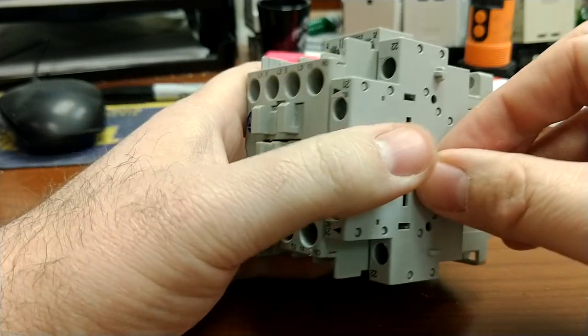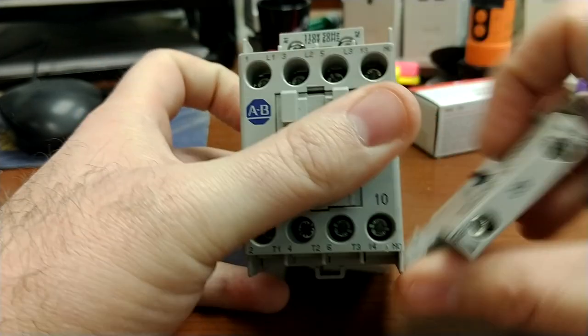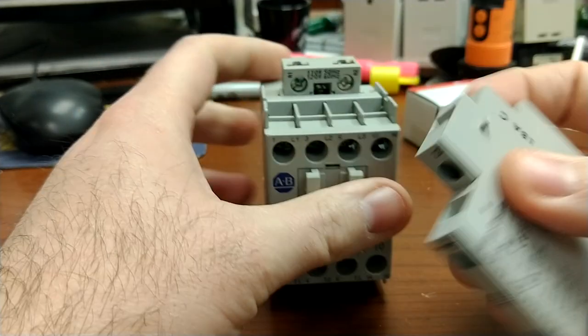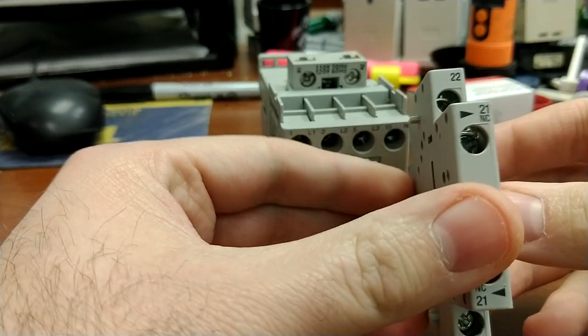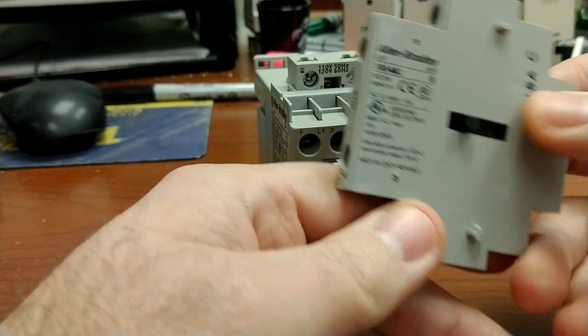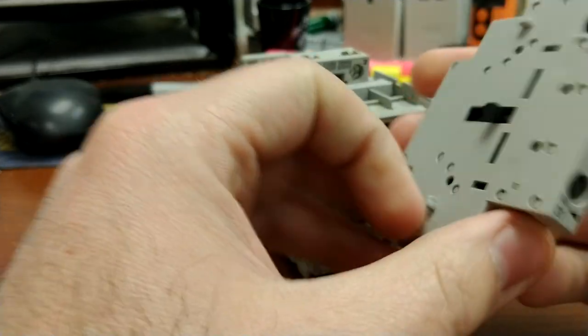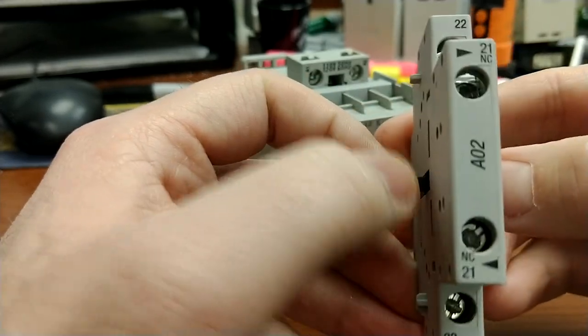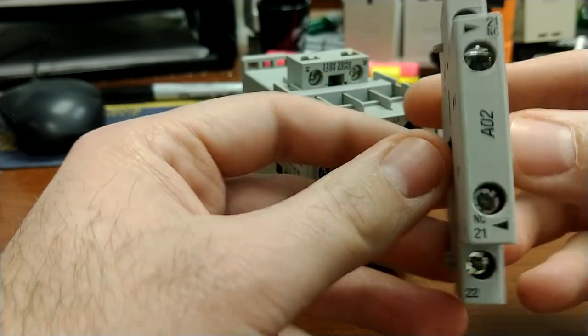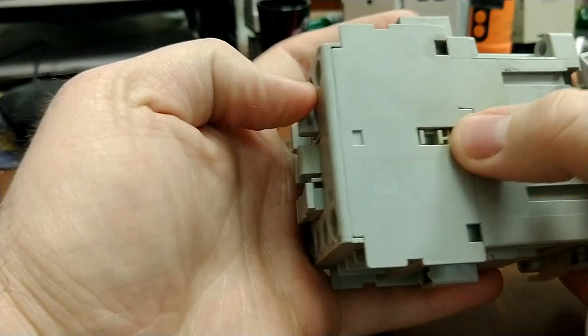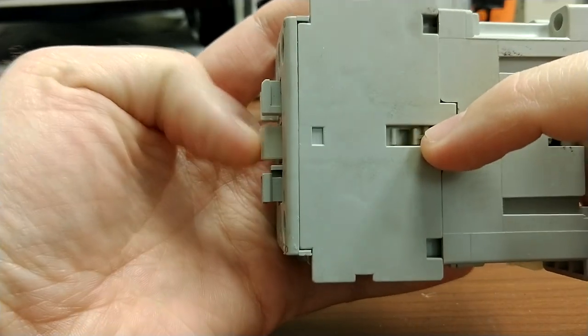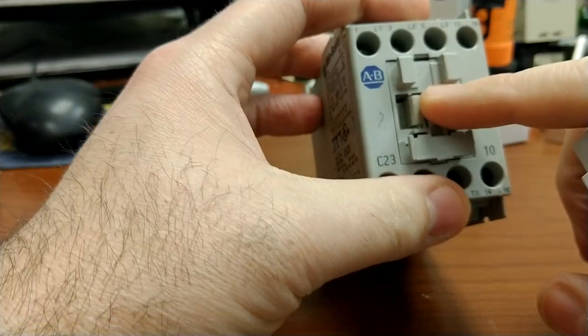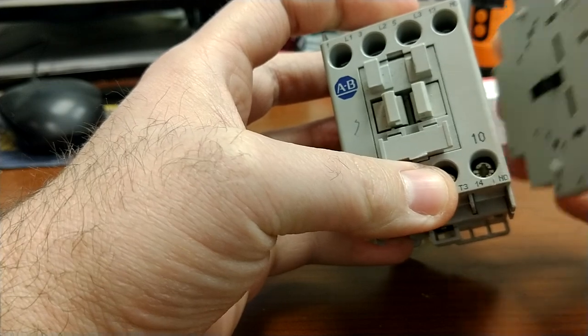Because oftentimes, we also have on the side, or in between, two of these set up in series with something like this in between it. It's an interlock that will keep the, and now this one's broken, so it's not, but you can see one is up, this is broken a little bit, but both are up. But if I extend one back, it will keep the other one from going forward, and vice versa.